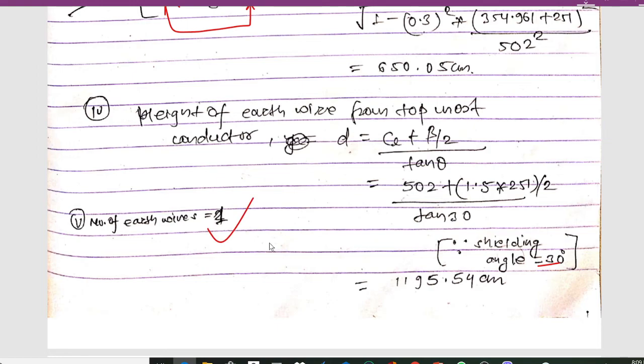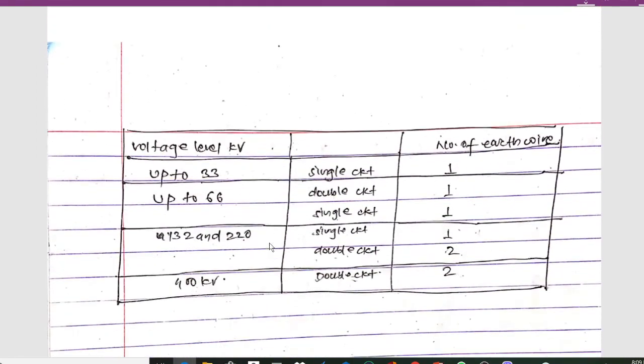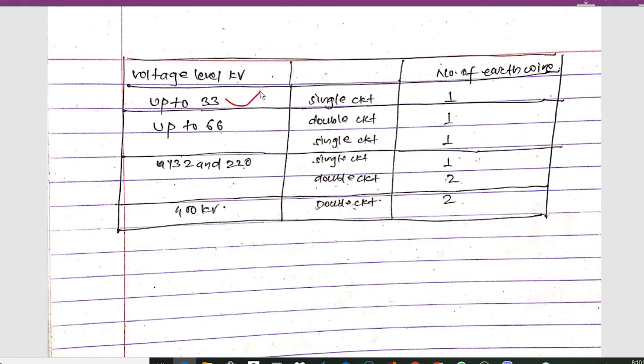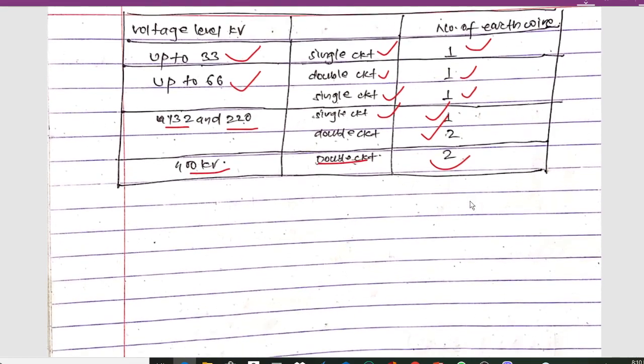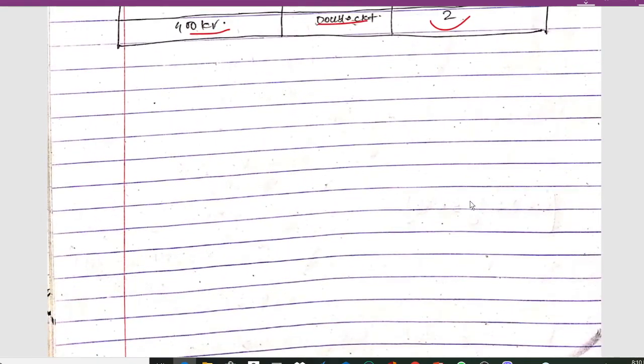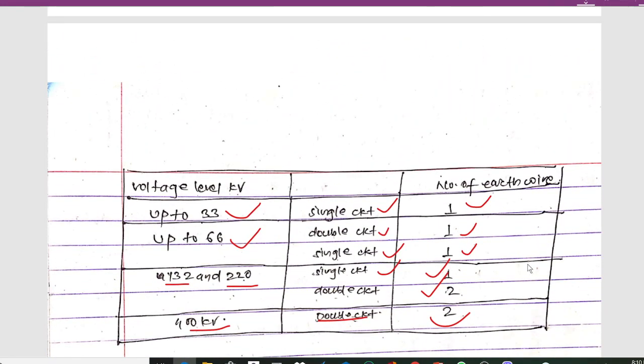The number of earth wires is determined from a standard table. For voltage levels up to 33 kV (single circuit): 1 earth wire. For 66 kV (single or double circuit): 1 earth wire. For 132 kV and 220 kV single circuit: 1 earth wire; double circuit: 2 earth wires. For 400 kV double circuit: 2 earth wires. Thanks for watching — please subscribe to my channel.